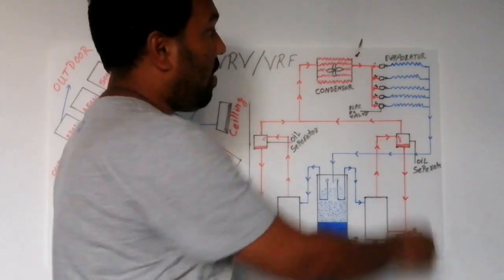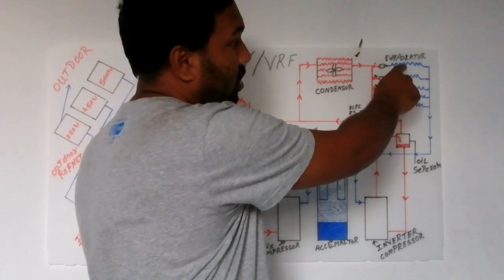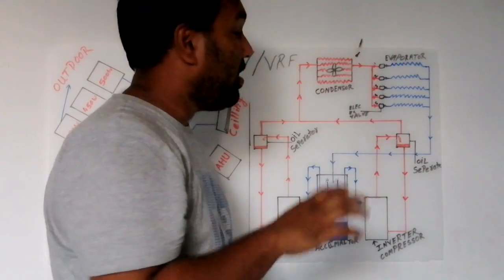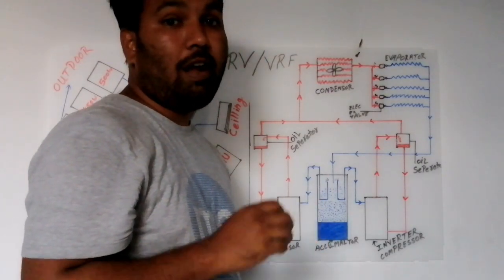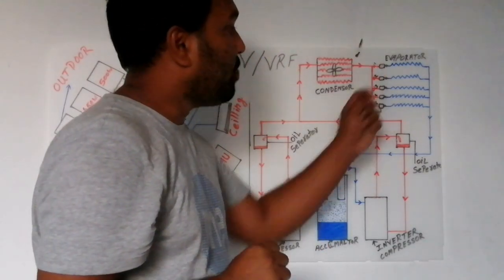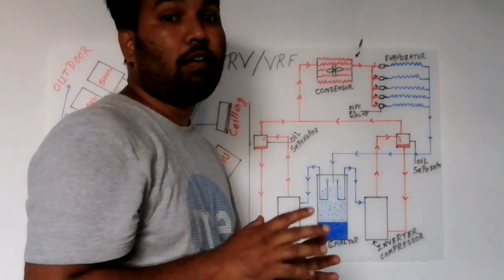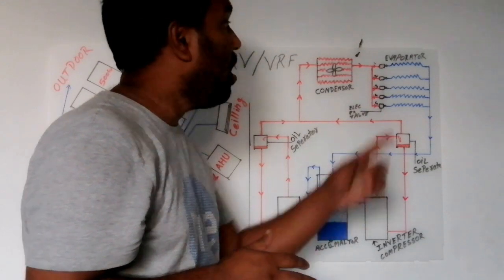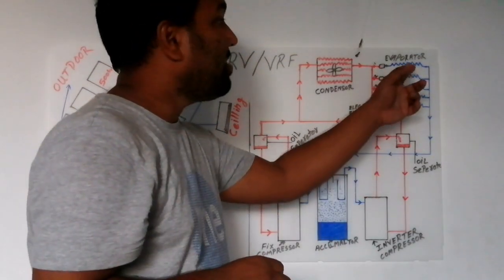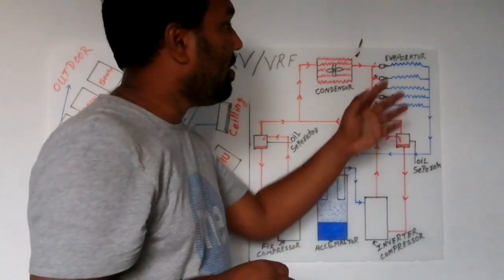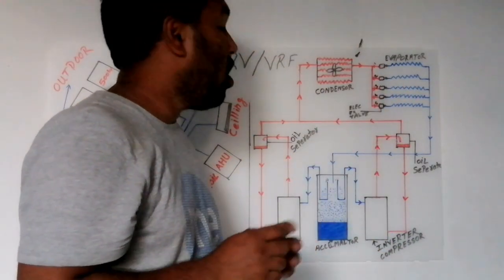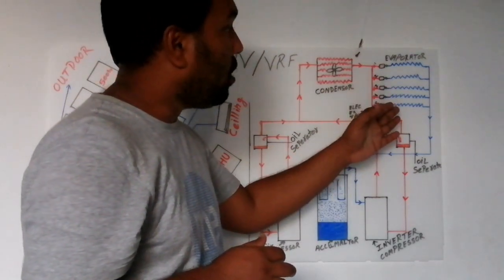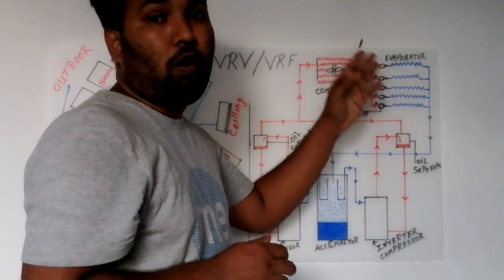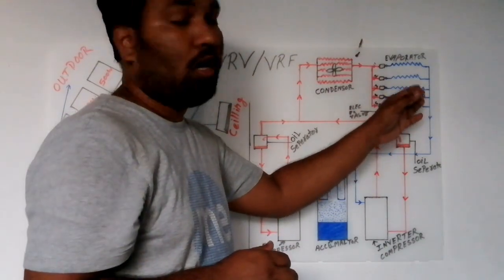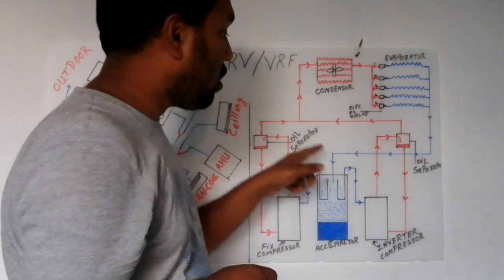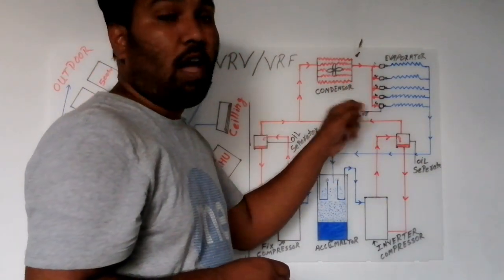For example, I have taken the first evaporator. In the first evaporator coil, I have set 24 degrees Celsius, and in that room we have 26 degrees Celsius. It means it is higher by 2 degrees Celsius. At that time, our expansion valve will open to the maximum, and it will try to give as much refrigerant as possible to the first evaporator coil. When it reaches the goal, when it has reached 23 degrees Celsius, at that time our expansion valve will be closed or minimized. And same for each evaporator coil. According to the requirement of cooling, our refrigerant flows to the evaporator coil. And this same process goes on continuously in our VRV and VRF unit.